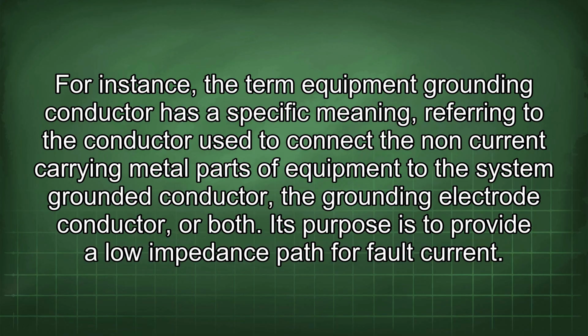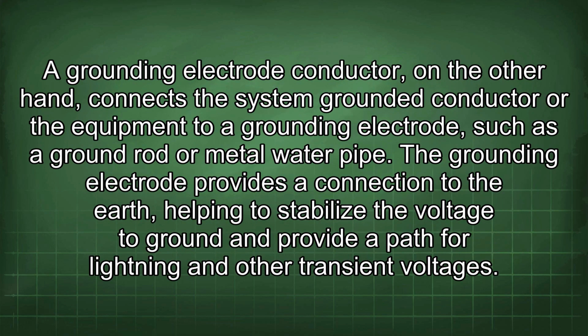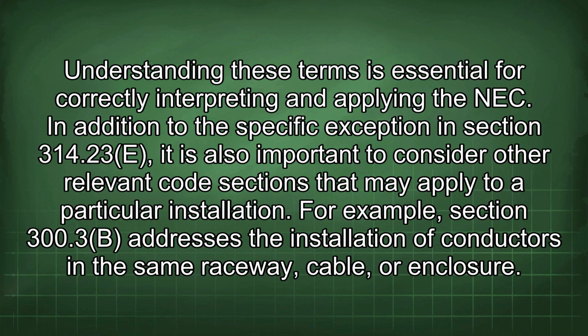Its purpose is to provide a low impedance path for fault current. A grounding electrode conductor, on the other hand, connects the system grounded conductor or the equipment to a grounding electrode, such as a ground rod or metal water pipe. The grounding electrode provides a connection to the earth, helping to stabilize the voltage to ground and provide a path for lightning and other transient voltages. Understanding these terms is essential for correctly interpreting and applying the NEC.